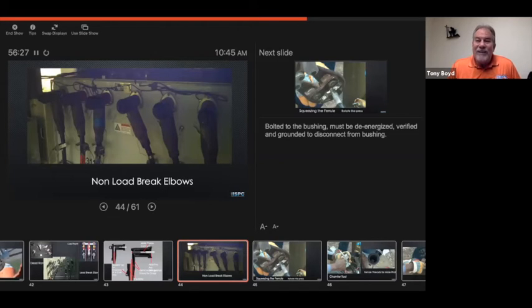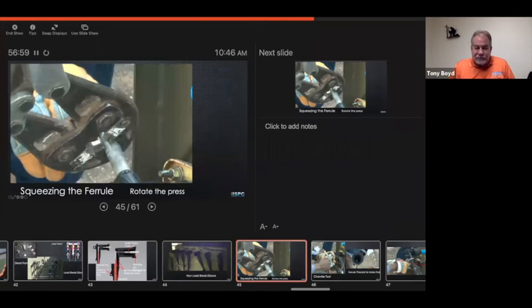Here are bolted on elbows. These are 600 amp elbows bolted onto a switch gear. You actually have a cap that's behind them. That cap can be pulled off, and we can add a bushing on there and add another 200 amp elbow onto this phase if we needed a tap or things like that. So very, very versatile. These are relays. This is actually a switch gear that has relays in an automatic switching scheme.